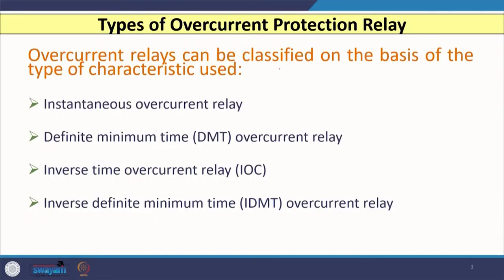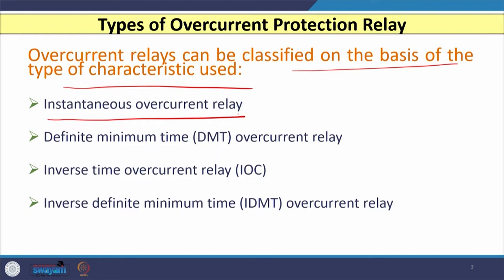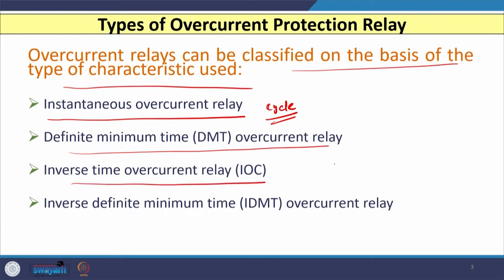Overcurrent relays can be classified based on the type of characteristic used. Basically four classifications are available. The first is based on time of operation: instantaneous overcurrent relays, which operate instantaneously — though no such relay exists in the actual field that operates instantaneously, so any relay that operates within one cycle is treated as instantaneous. The second type is the definite minimum time overcurrent relay. The third is the inverse time overcurrent relay, and the fourth is the inverse definite minimum time (IDMT) overcurrent relay.